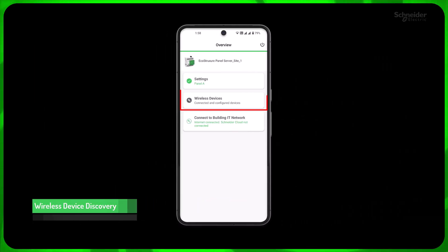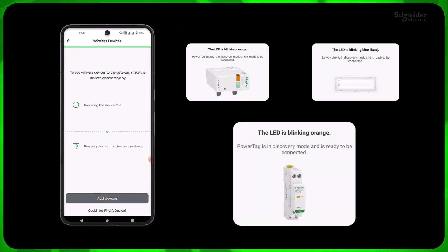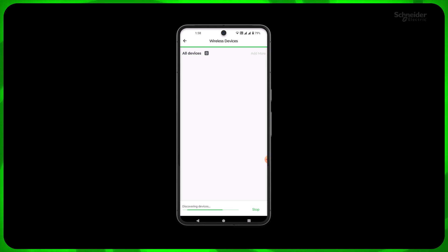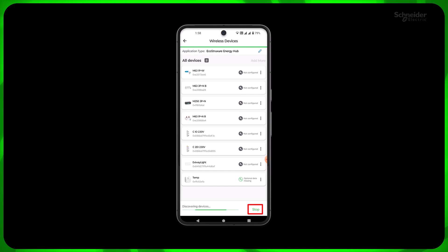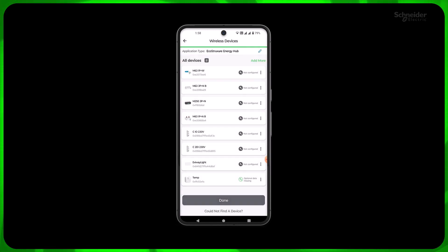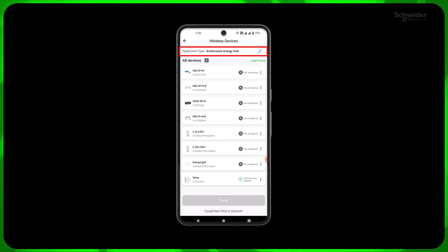Click on wireless devices to add the required devices. Please make sure the devices are on and ready to pair. In this site, we have wireless devices like PowerTag Energy, PowerTag Control, PowerTag Ambient, and Exiway Emergency Light. Click Stop if all your devices are discovered. Make sure the application type is selected as EcoStruxure Energy Hub.